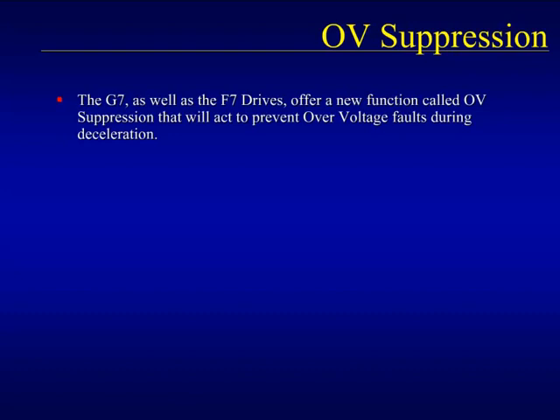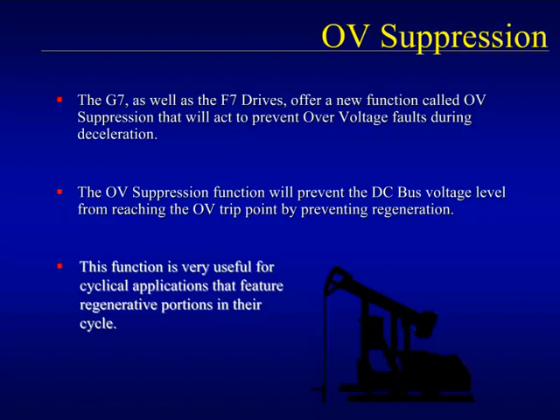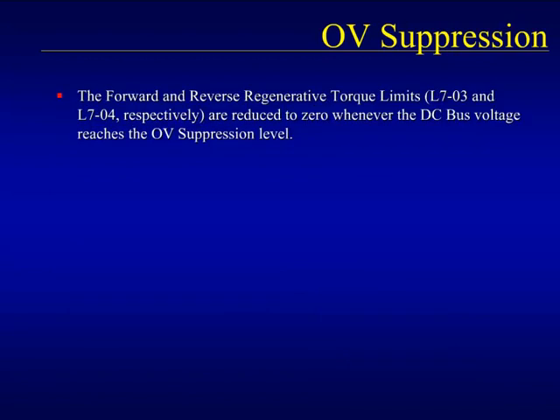The final new G7 function we will cover in this eLearning module is the overvoltage suppression function. Both the G7 and F7 drives feature OV suppression that will act to prevent some overvoltage faults during motor regeneration. The goal of OV suppression is to prevent excess power regenerated back to the drive during deceleration or from an overhauling load from raising the DC bus voltage to its trip level. Successful use of OV suppression will be very useful for cyclic applications that feature a regenerative portion to their cycle, such as the pump jack shown here. The OV suppression function prevents the DC bus from reaching trip levels by dropping the regenerative torque limit to zero whenever the bus voltage reaches a certain level.